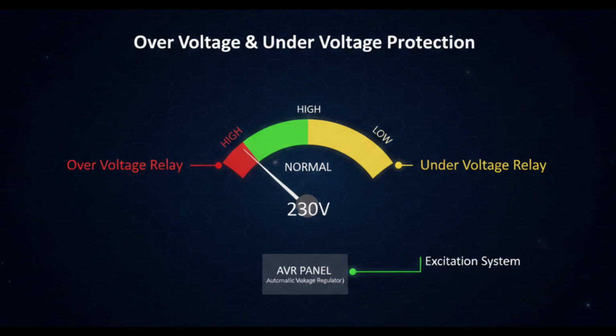Over voltage or under voltage protection. Voltage must stay within safe limits. If voltage becomes too high, insulation of equipment may break down. If voltage becomes too low, motors may stall and overheat. Over voltage may occur due to AVR malfunction. Under voltage may occur during heavy load or generator issues. Voltage relays continuously monitor system voltage. If voltage exceeds safe range, alarm or trip is activated. Stable voltage ensures proper functioning of all electrical equipment. Regular checking of AVR settings helps maintain voltage stability.